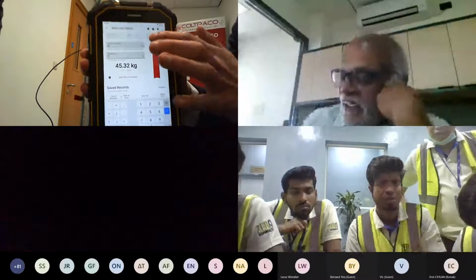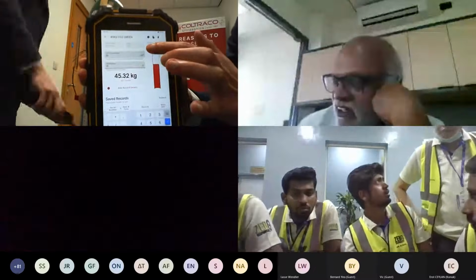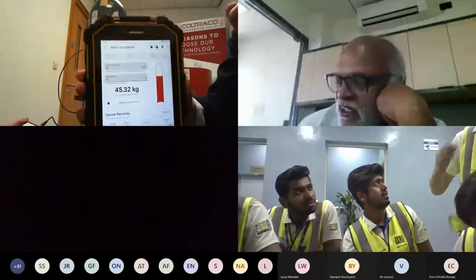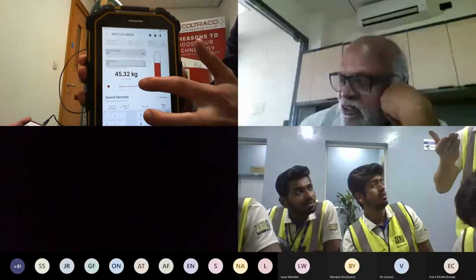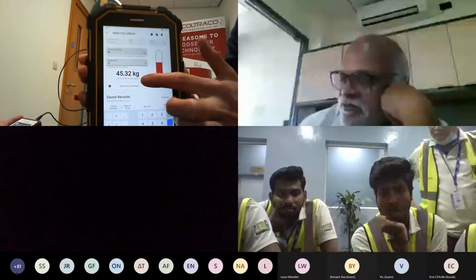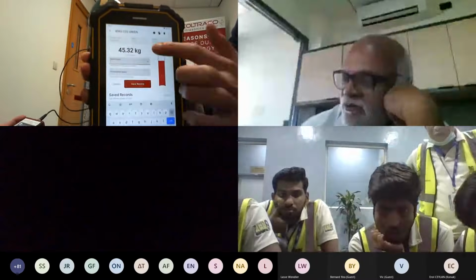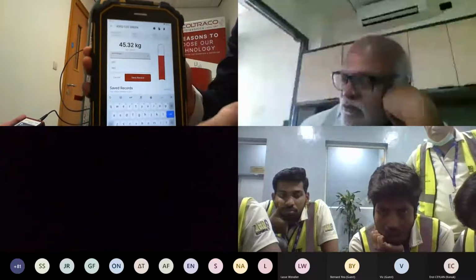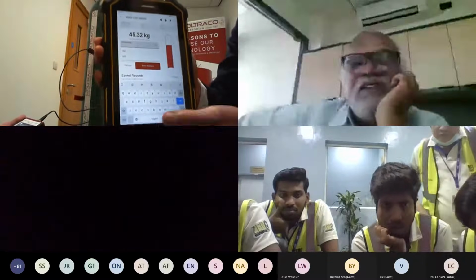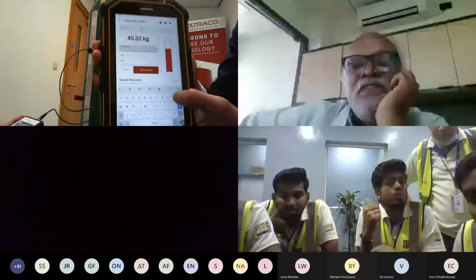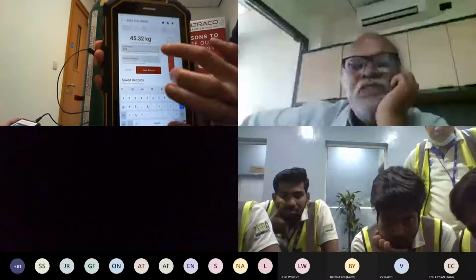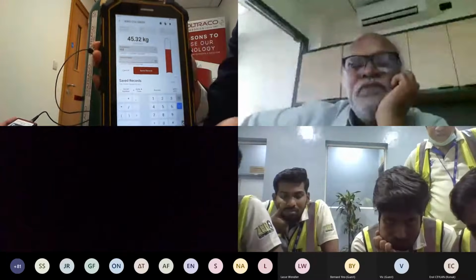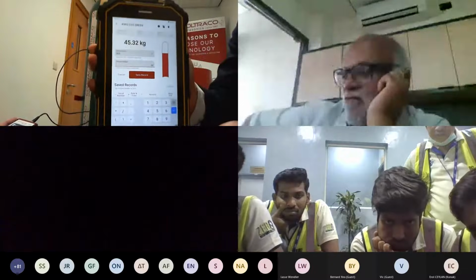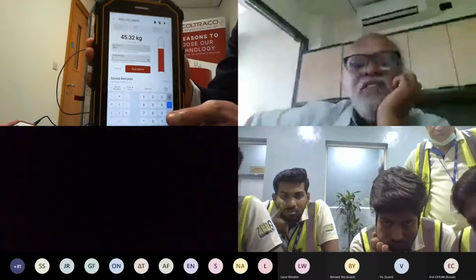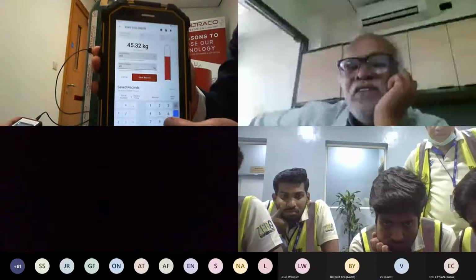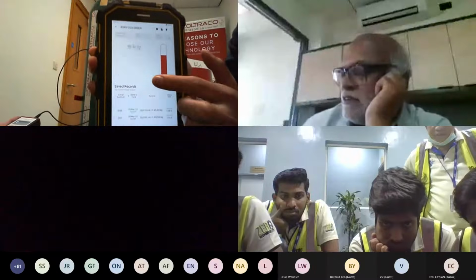So as you can see, with the liquid level height of 99 and a temperature of 11 degrees, the agent weight is 45.3 kilograms. So I will press add record details, and I can include the serial number of the cylinder. Let's say the serial number of the cylinder is 003. You can then put in the printed fill mass. The printed fill mass is the weight that is already printed on the cylinder. So if this is 45 kg, I will put 45 kg and I'll press save record.